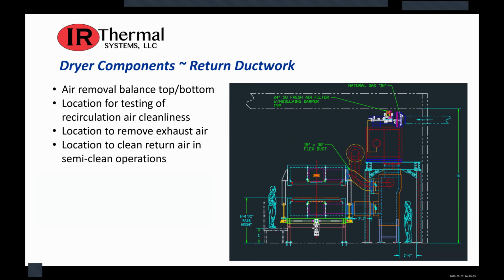The return ductwork, once again, if I'm trying to supply air as evenly as possible, it's important to remove that air as evenly as possible, in order to not cause web shifts or web disturbances. So I typically will have dampers for balancing the top to bottom air. It's a great location for air testing for cleanliness or particulate, as well as removing messes from web breaks.